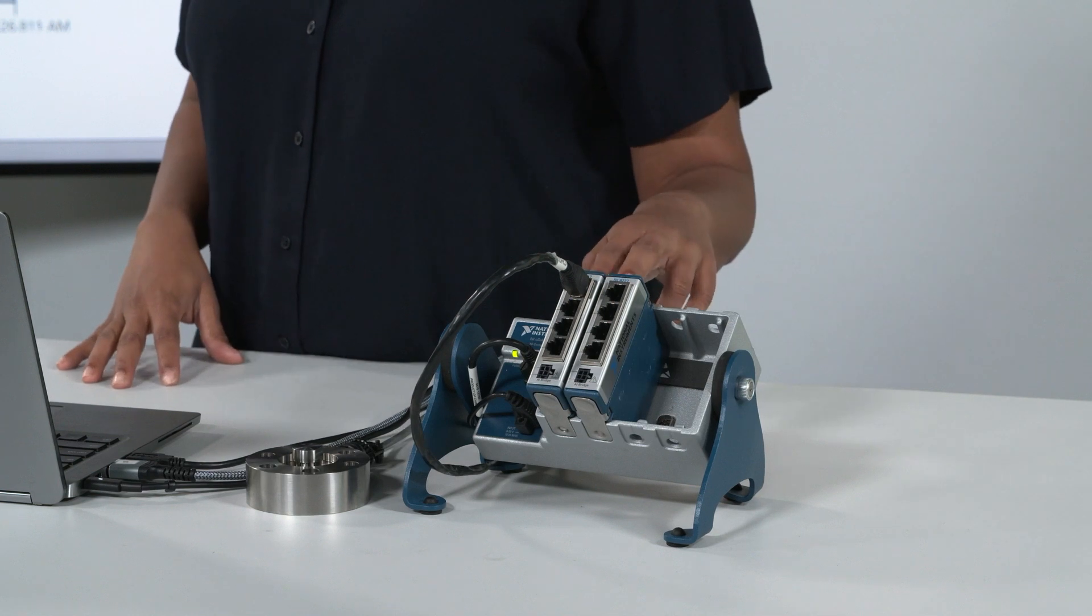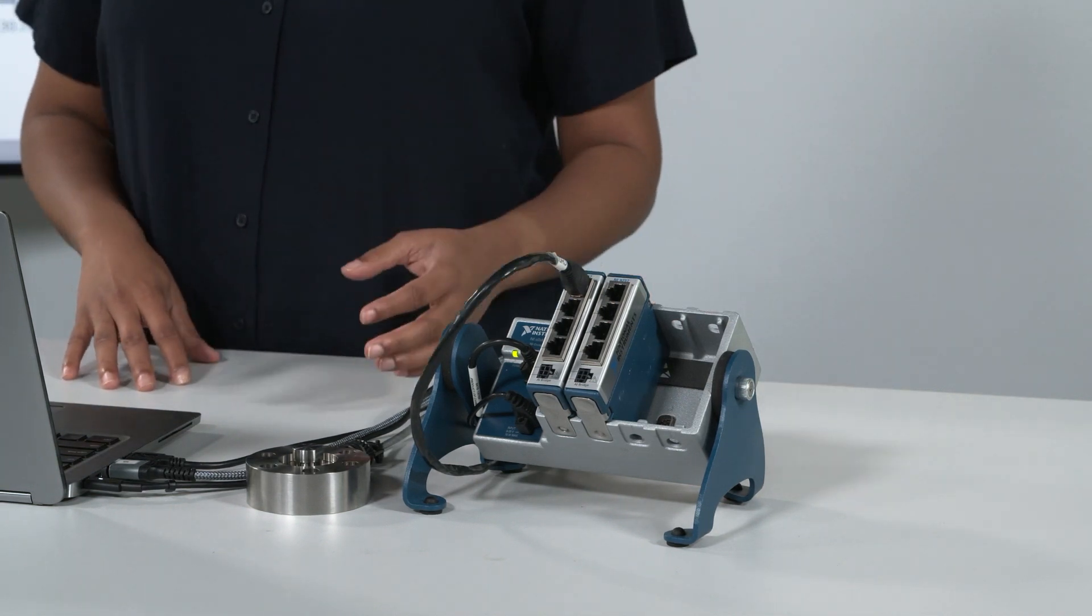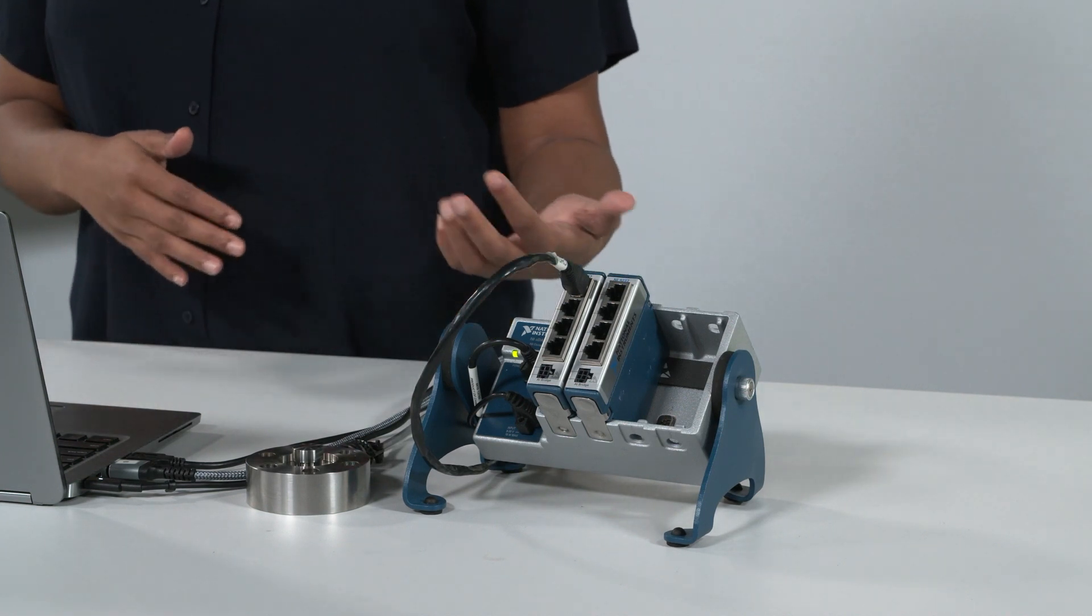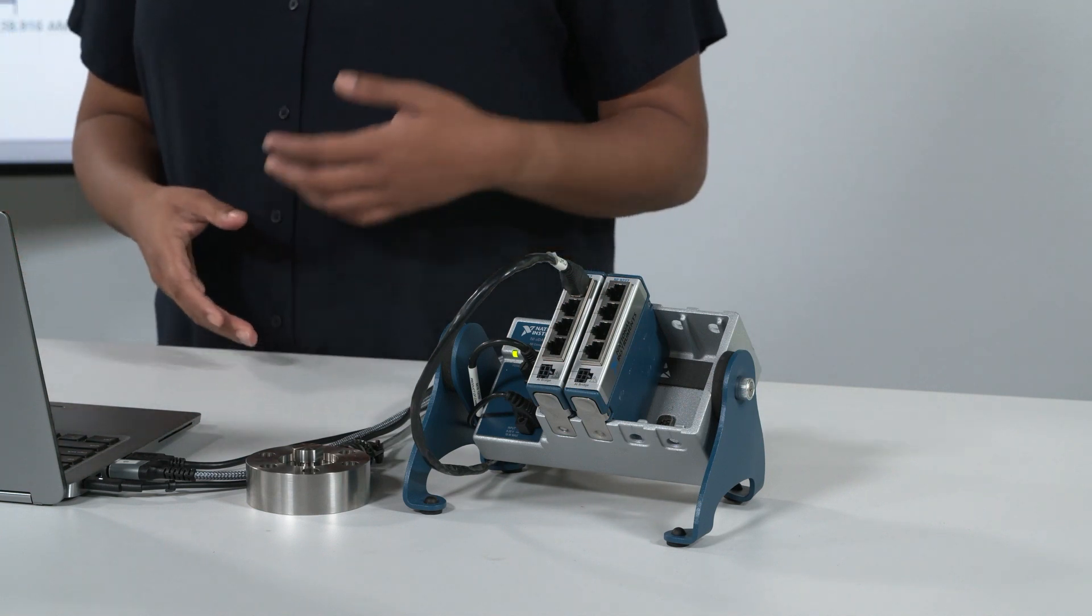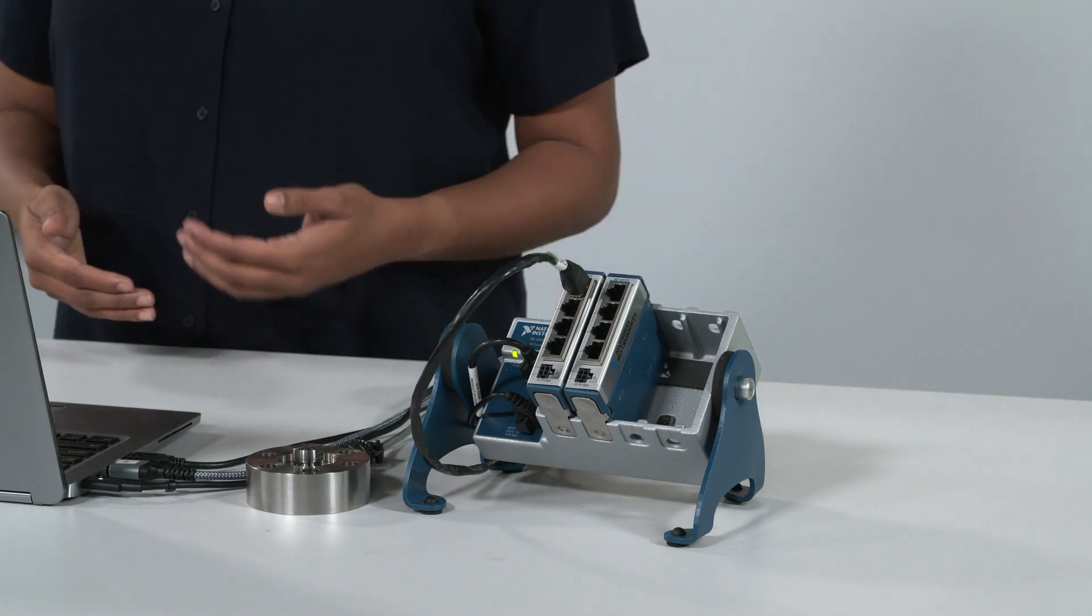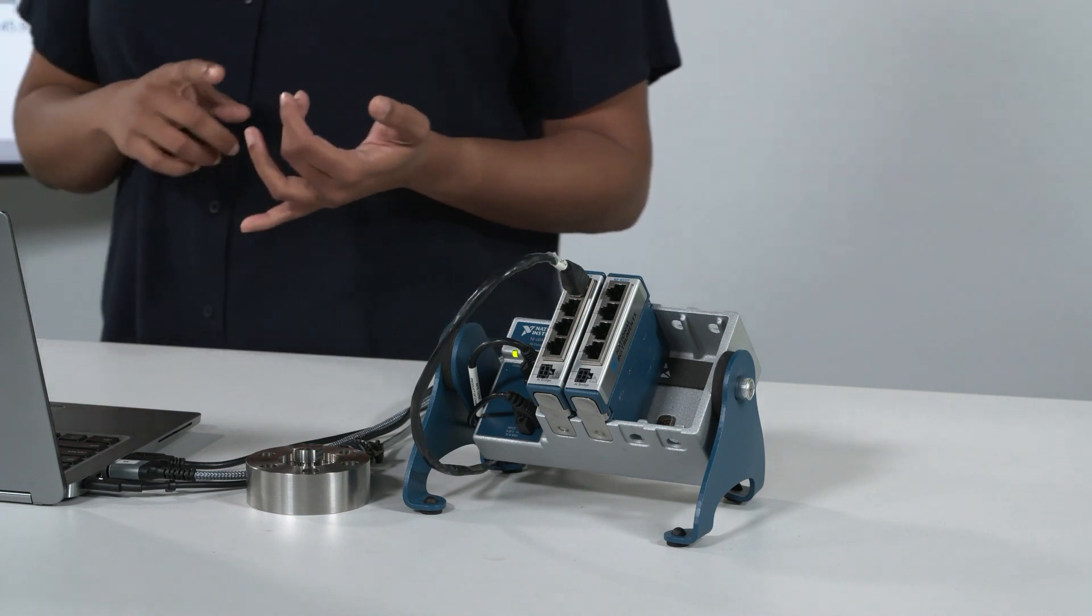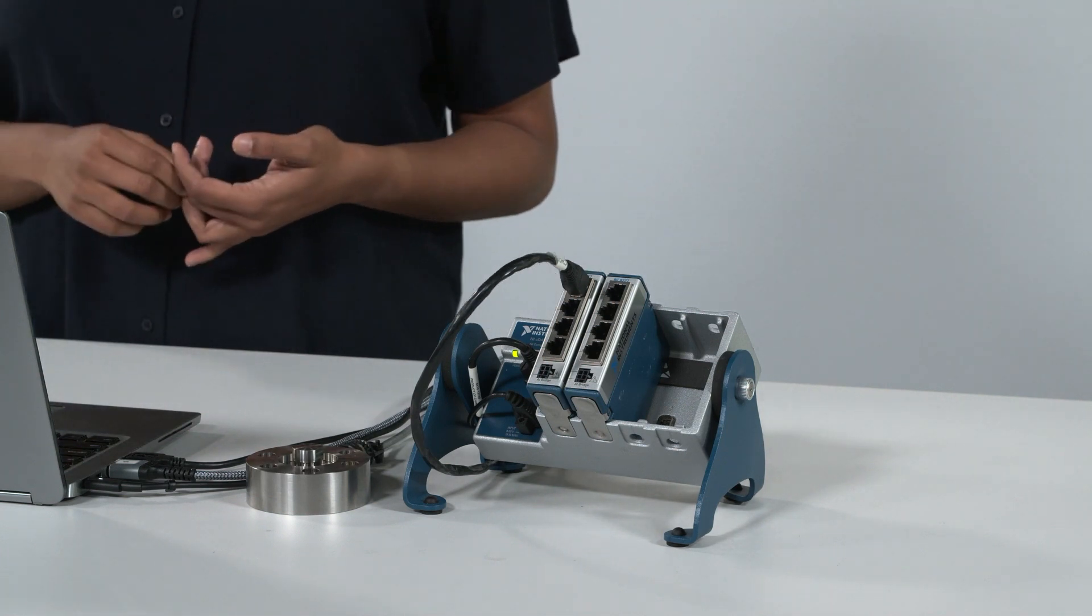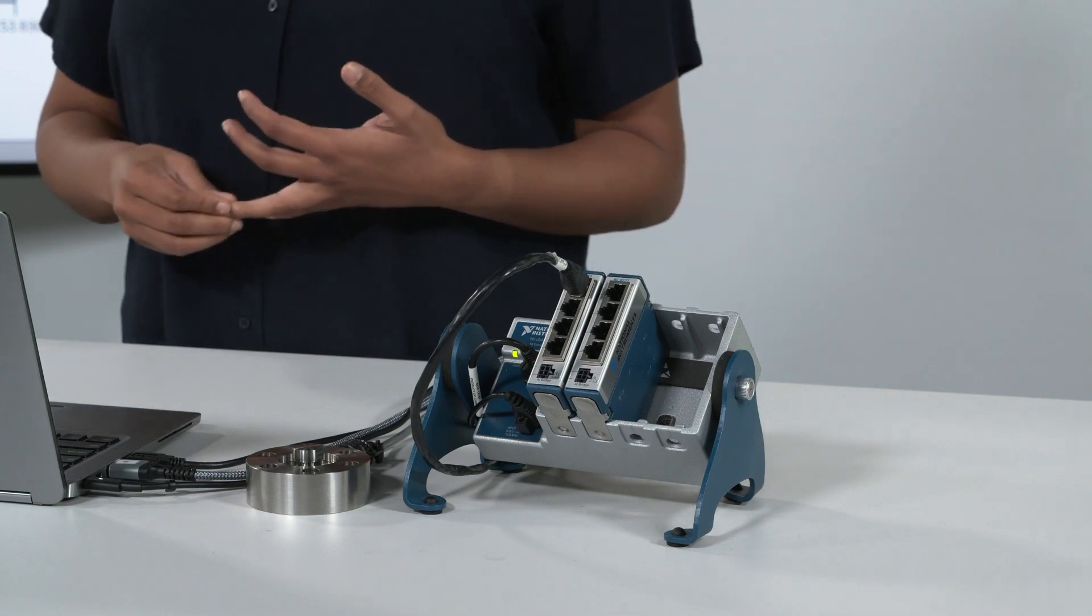The modules in the system are the 9237s. These are specifically designed for strain and load. What that means is while NI has generic analog input and output modules, this is specifically designed and specially made, so it has some of those basic modifications, such as bridge completion of 120 to 350 ohms, as well as dynamic measurements up to 50 kilosamples.